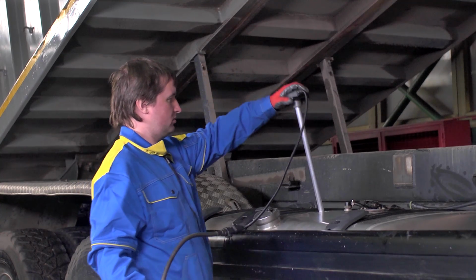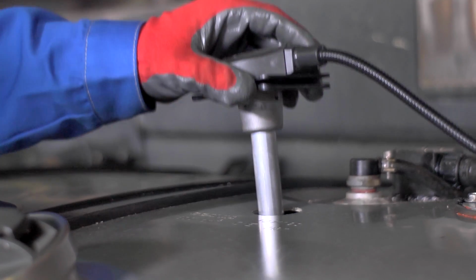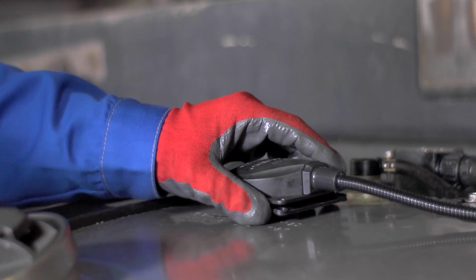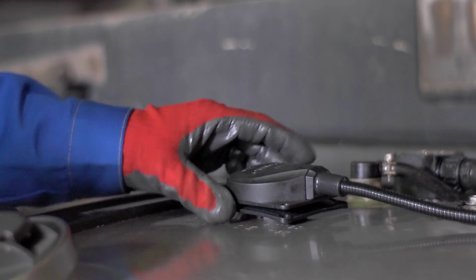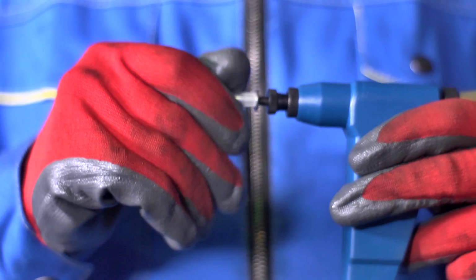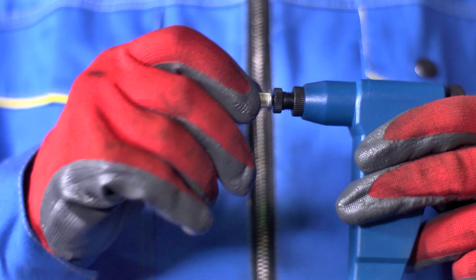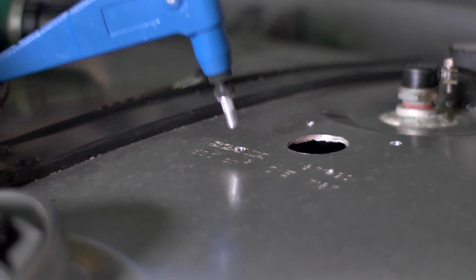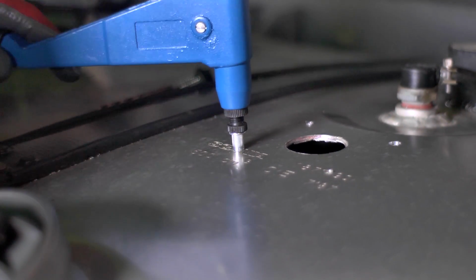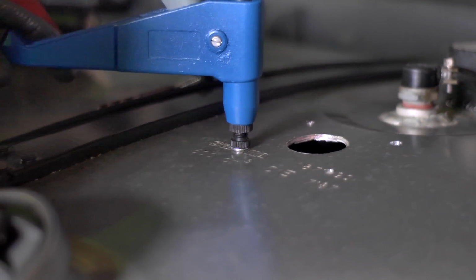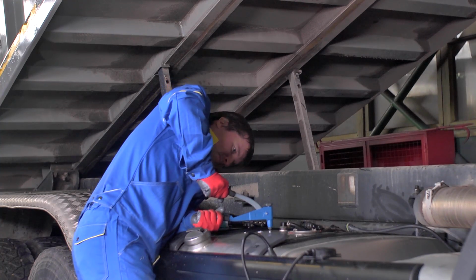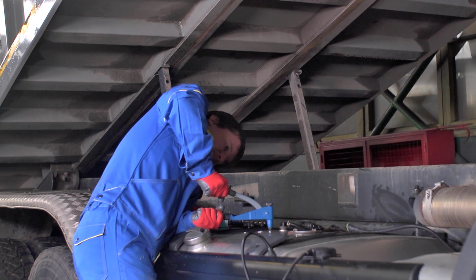Perform a final fitting to make sure that you have chosen the right length and correctly marked the screw or rivet holes. The sensor delivery kit includes self-tapping screws and threaded rivets. You will need a special riveting tool to pin the rivets. Use it to pin the rivets into holes drilled in the tank in advance.